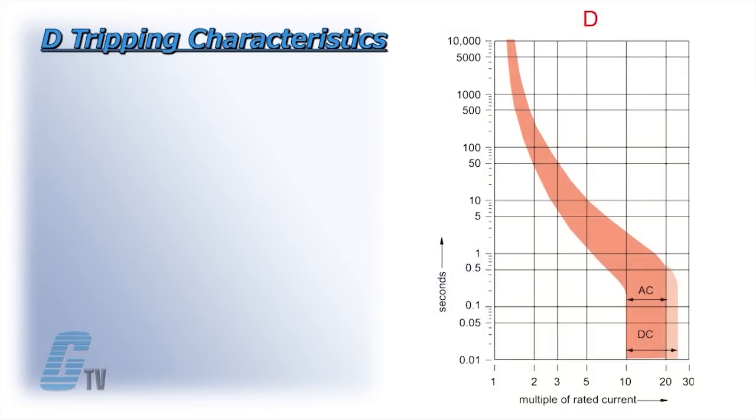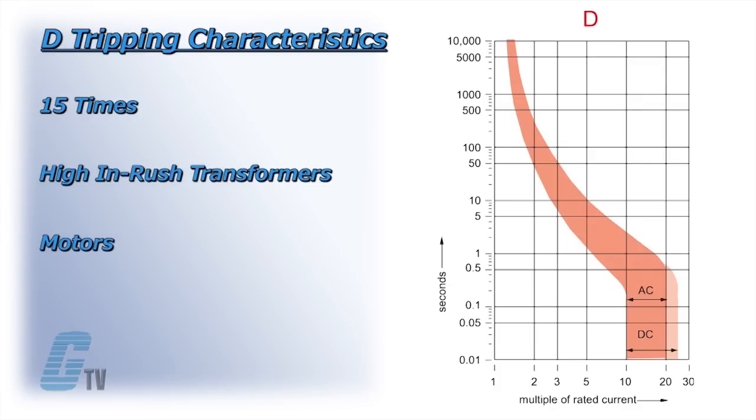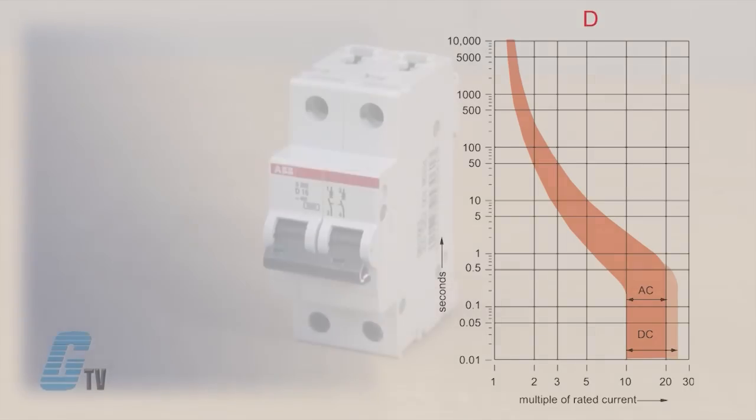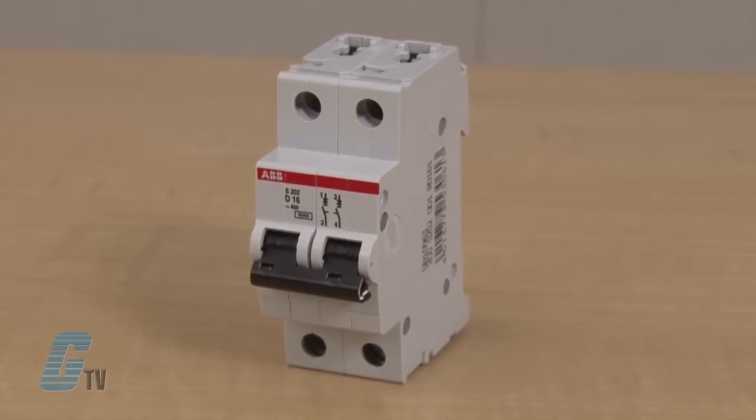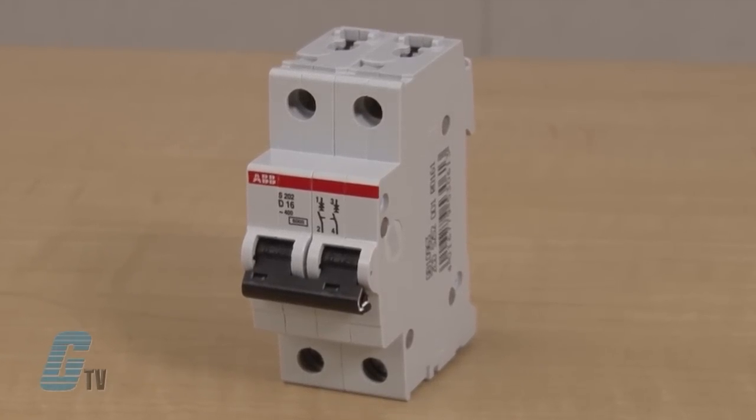The D tripping characteristic has a new magnetic trip action with an instantaneous trip point of approximately 15 times the breaker rating. The S200 D breaker can be a good protective solution for applications involving high in-rush transformers, motors, and other high inductive systems. The S200 D is also suitable for any application where a high instantaneous trip point is desired.